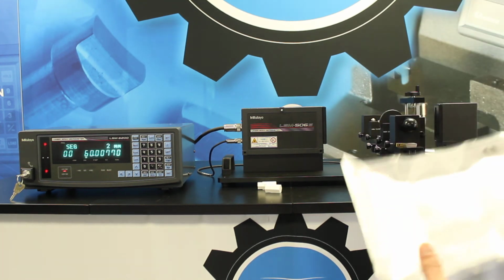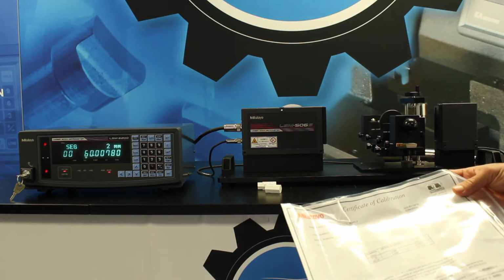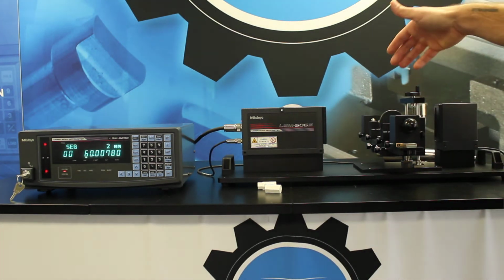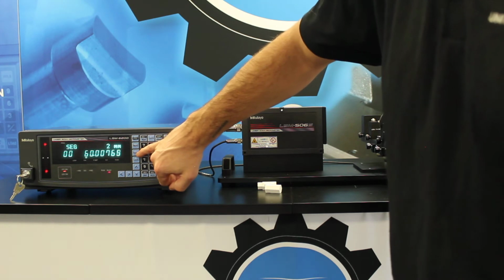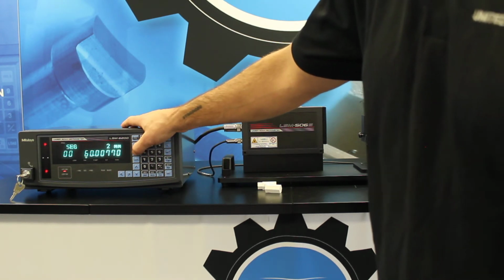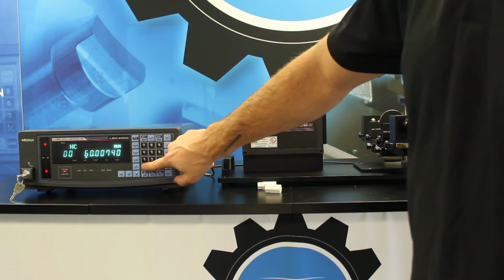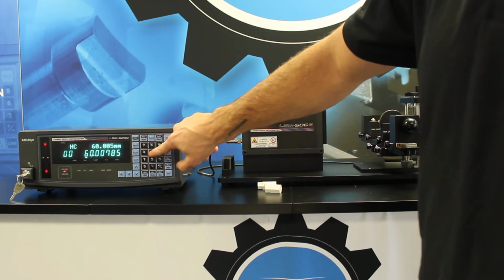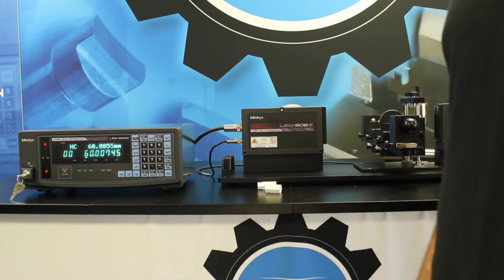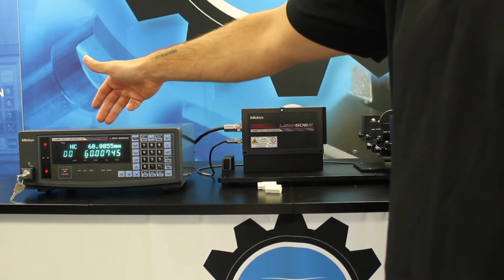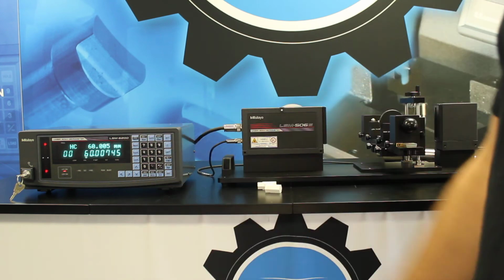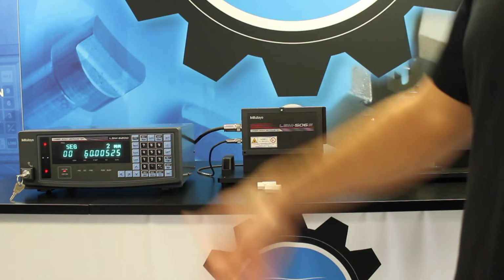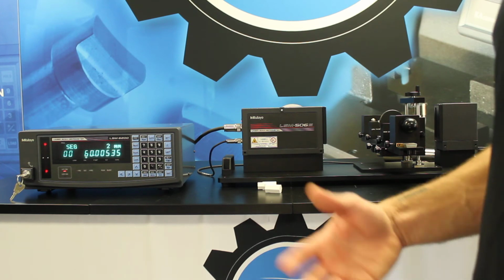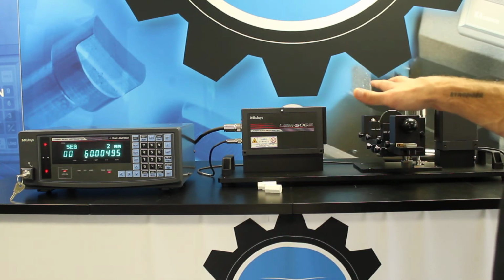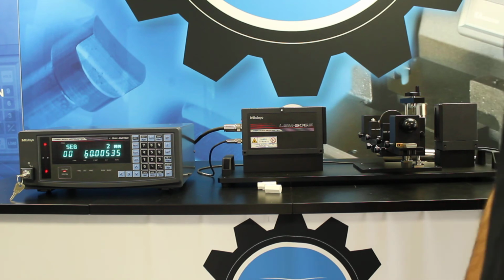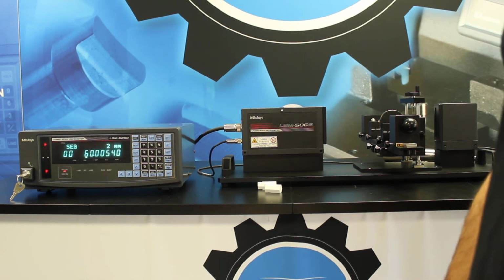My artifact has a certificate at 60 millimeter 5.5 micron. So since I'm doing the high calibration, there is an HCal key here on the readout. I'm going to press the HCal key, key in my value of 60.0055, hit enter. Once I hit enter, the input value will blink a couple seconds, the readout's going to freeze, and eventually it's going to recognize that value input. Keep in mind we are in sub-micron here and I'm not in a lab environment, so we are going to see those last 2 digits flicker back and forth.